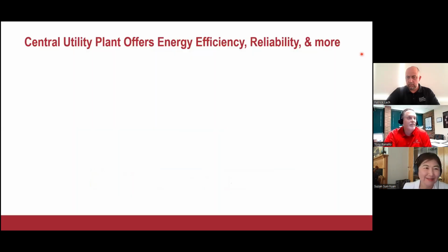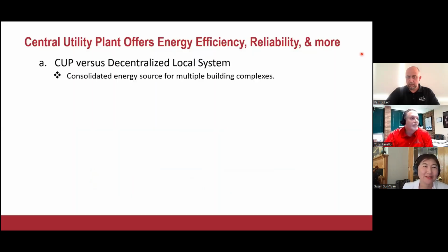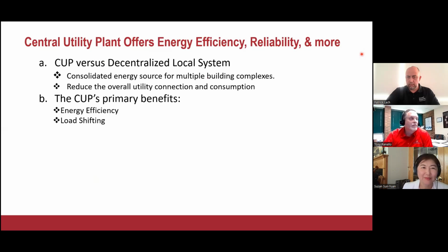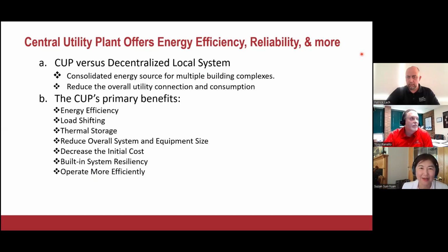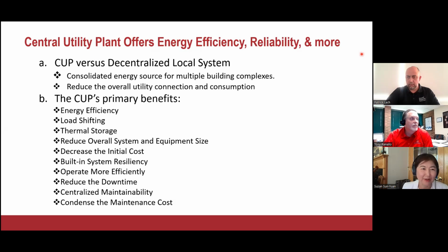Next slide, please. The choice between the central utility plant, CUP, and the decentralized system depends on factors like energy demand, geographical conditions, and the desired level of control and resilience. When the facility reaches a certain capacity, the benefits of a CUP become apparent, such as energy efficiency improvement, load shifting within campus, and built-in thermal mass via a distribution network.